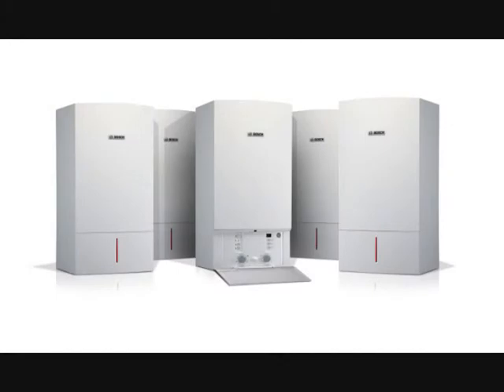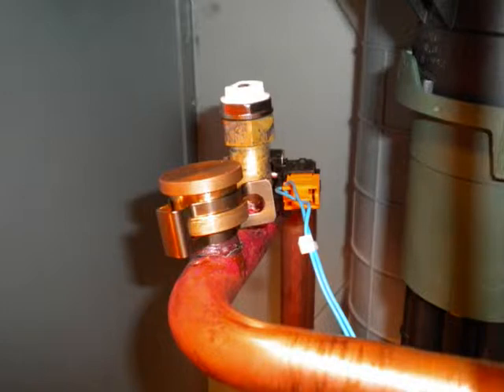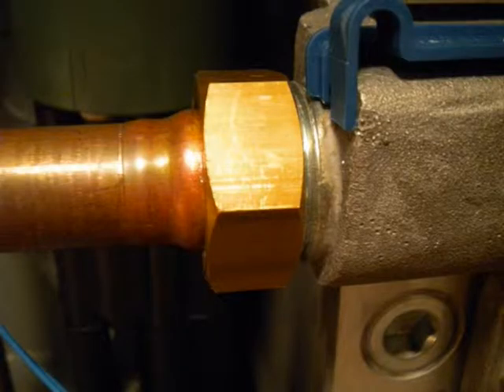Let's get started. After installing your Greenstar boiler, fill and purge the system of air. On the heat-only boiler, remove any residual air in the heat exchanger by using the manual air vent located just to the left of the heat exchanger on the supply pipe. On combi boilers, any residual air in the heat exchanger can be removed by slightly loosening the brass supply pipe union.